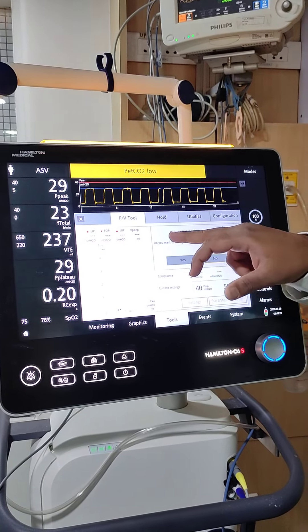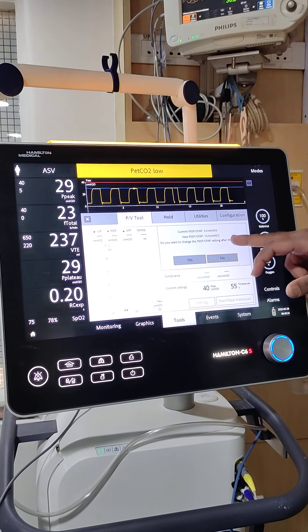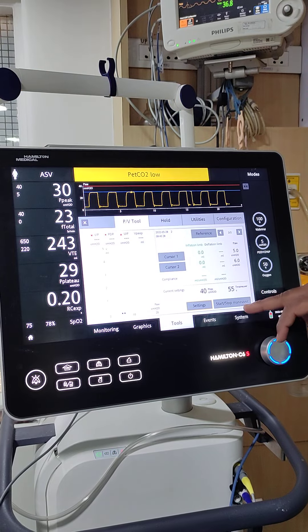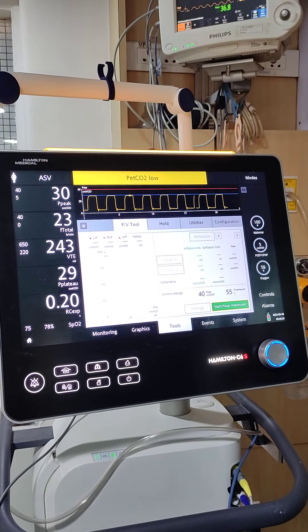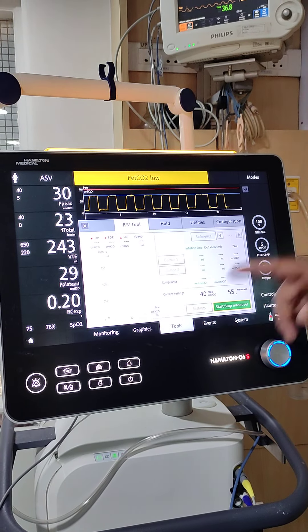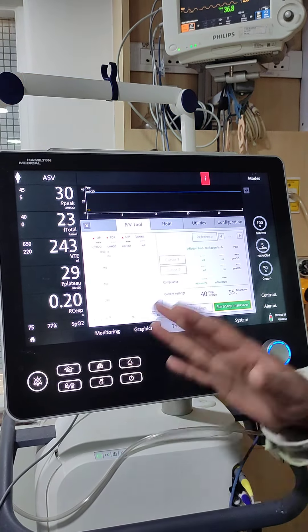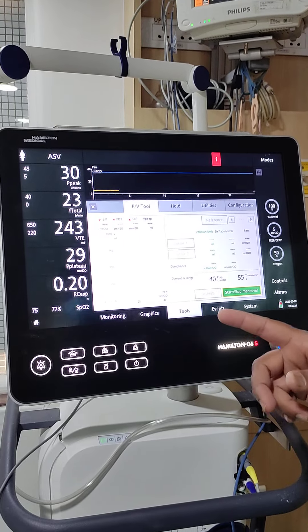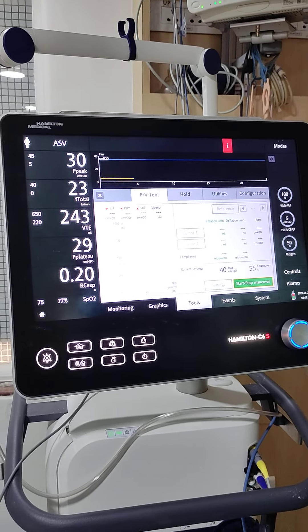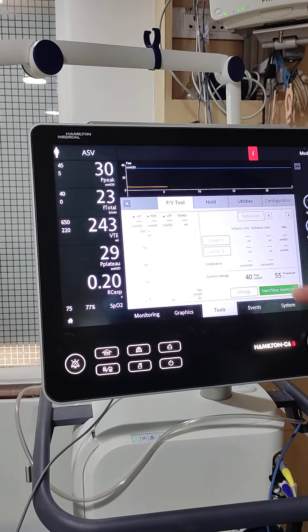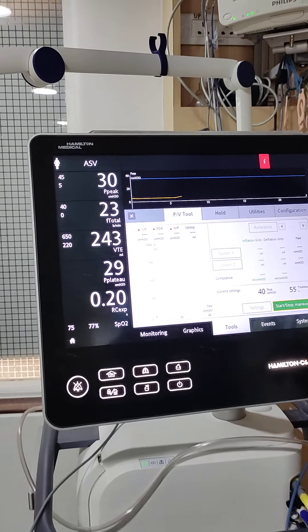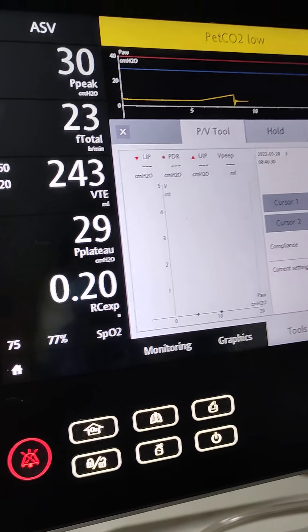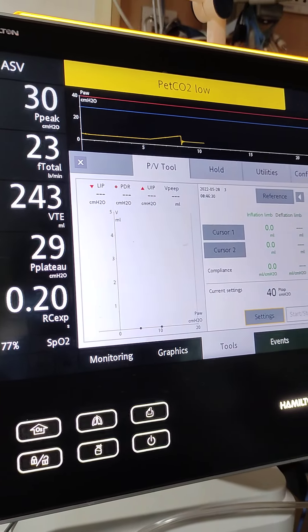Current PEEP is 5. I want to change my PEEP — so I want to make it 15. I start the maneuver now. Now it is starting the recruitment. Now you see how it is going to look like. Yesterday we did not do the recruitment, so now see how it is going to do. Now it is starting the recruitment maneuver.